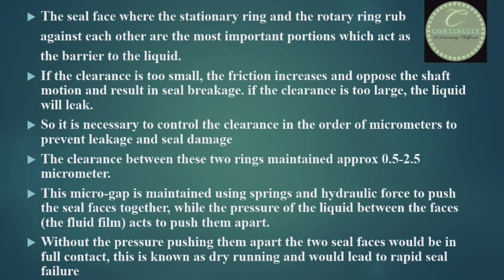This micro gap is maintained using springs and hydraulic force, pushing the seal faces together, while the pressure of the fluid film between the faces pushes them apart in the order of micrometers. Without this fluid film pushing them apart, both seal faces would be in full contact — this is known as dry running — and would lead to rapid seal failure.